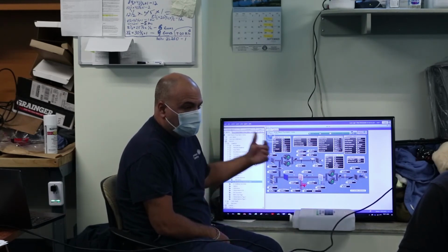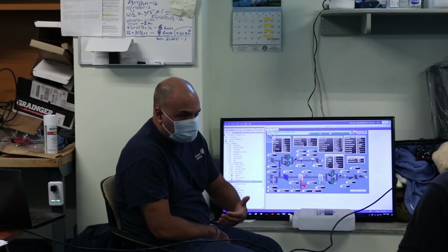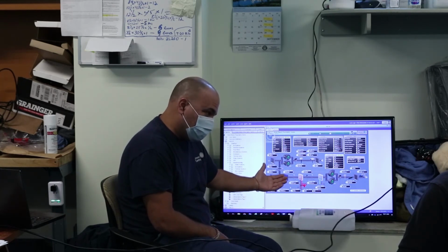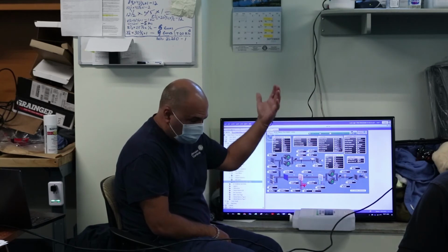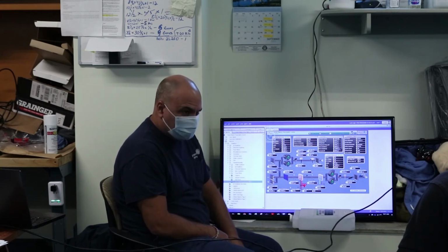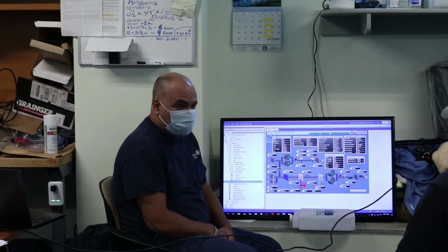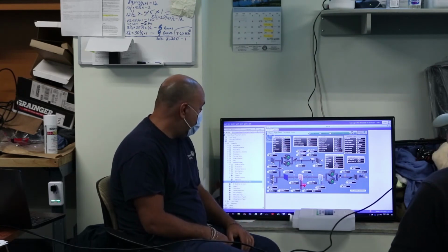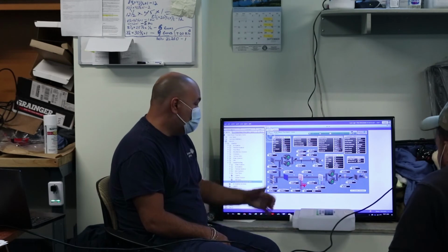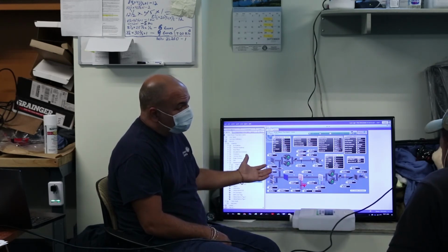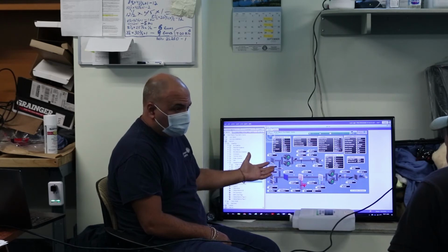So you may be heating more than your preheat temperature if your DAT is higher, or you may just be looking at 50. I don't see your DAT being lower than 55 in a winter. So you can run into the scenario where your heating and cooling valves are open at the same time, where you really shouldn't.